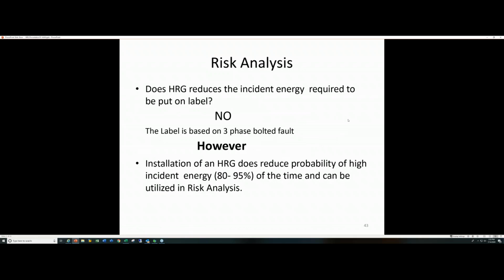So let's talk about it. Does an HRG reduce the incident energy required to be put on the label? Well, not really. When you're doing your studies, and many of you I'm sure have done your arc flash studies, the labeling for your hazard category is based off a three-phase bolted fault. So it doesn't reduce your label. However, like I said earlier, it does have a higher probability of incident energy reduction of 80 to 95%. And you can use that in your risk analysis now. With NFPA 70E 2018, it's a whole new concept of allowing for risk assessment. And that comes into play as you're designing or retrofitting stuff as well.